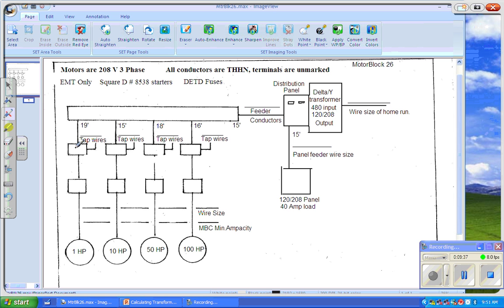Let's say that we have our control transformer in our largest motor starter. That means we're going to have a little control transformer in here, and we might be taking a pair of wires to each. Actually, I've drawn that incorrectly, haven't I? Let's try that again. If we have a little control transformer in this motor starter, we're going to have to bring our supply down to each motor starter, right?